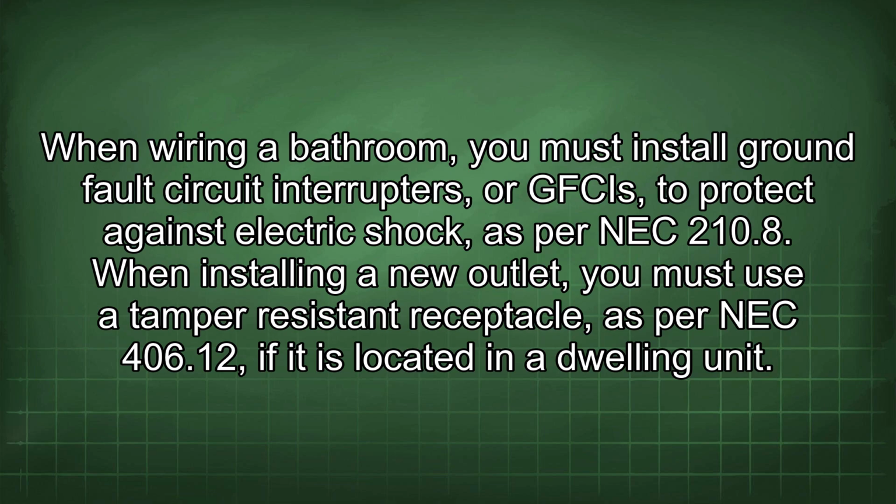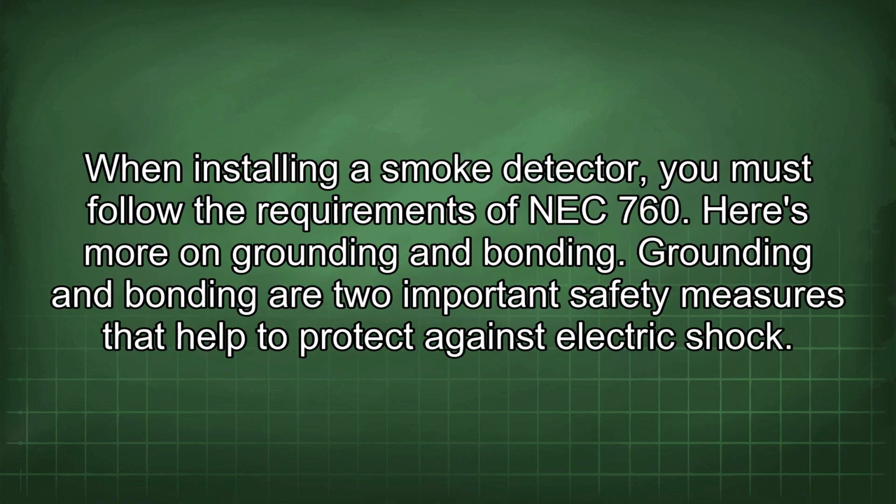as per NEC 210.8. When installing a new outlet, you must use a tamper-resistant receptacle, as per NEC 406.12, if it is located in a dwelling unit. When installing a smoke detector, you must follow the requirements of NEC 760. Here's more on grounding and bonding.